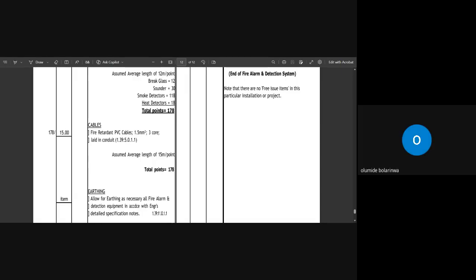Yes, right. I was telling you that your average length in this take-off is 15. But sometimes you might have a single core cable or 3 core. If you're using a single core cable, you must multiply it by 3 times the number of devices you want to use. But this take-off says 3 core, so I'm not multiplying by 3. It shows that in one package of cable, you have 3 cables serving as 3 core. Are you there with me? Do you understand?